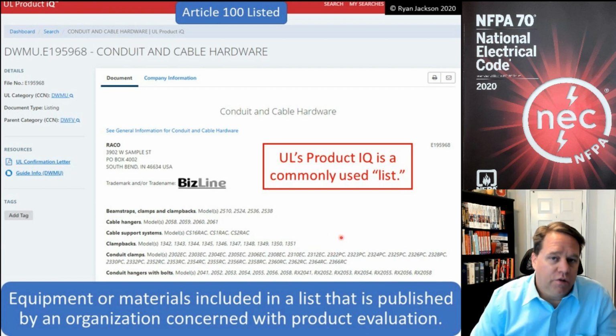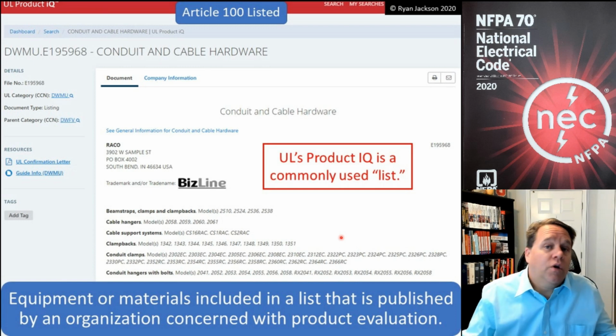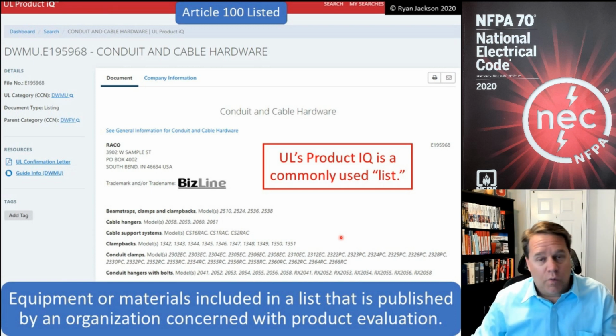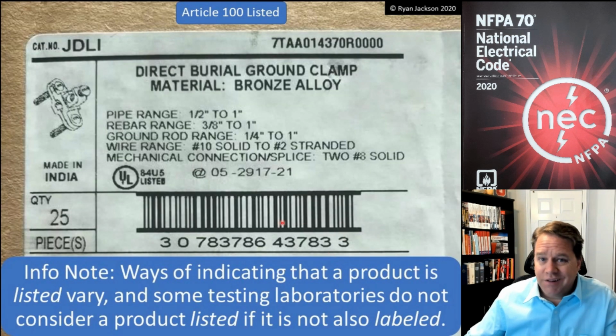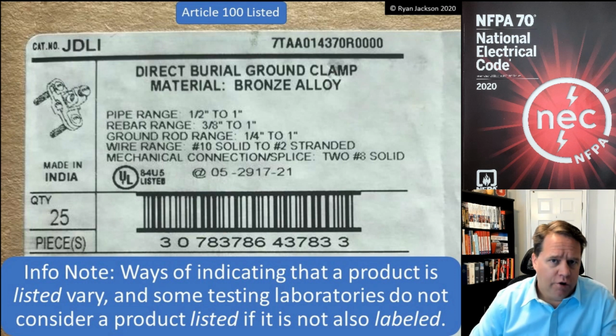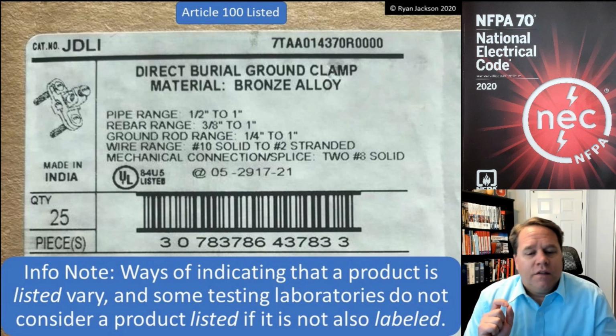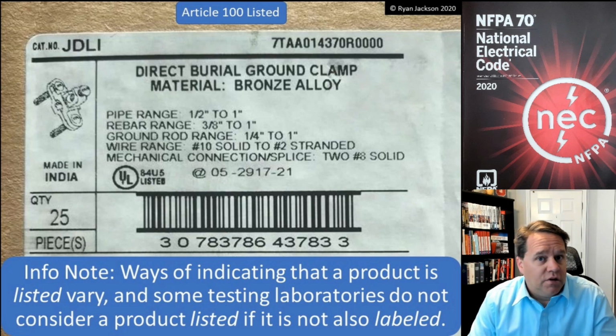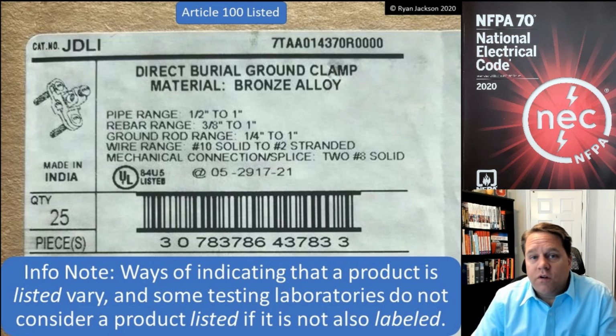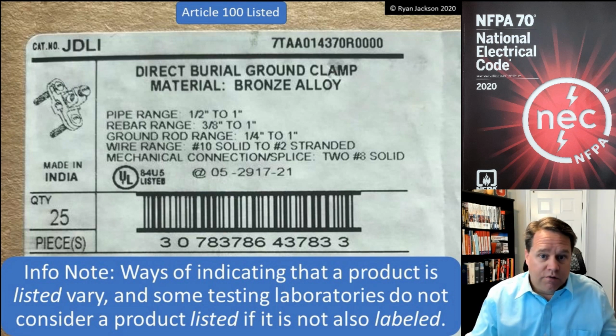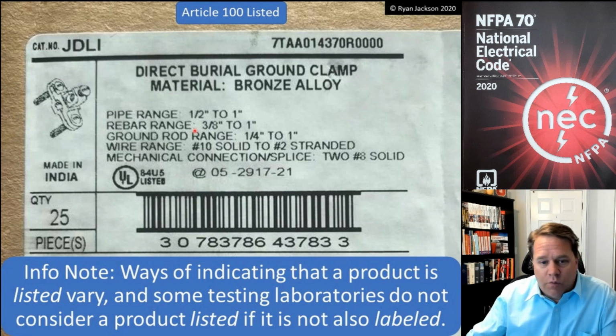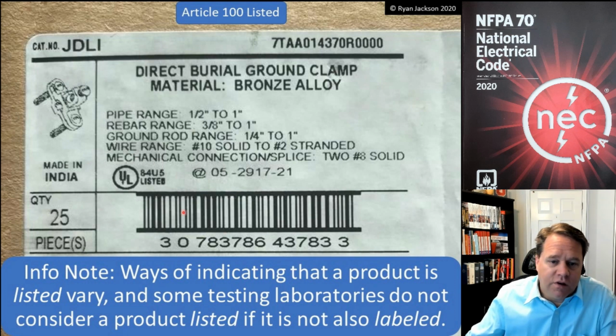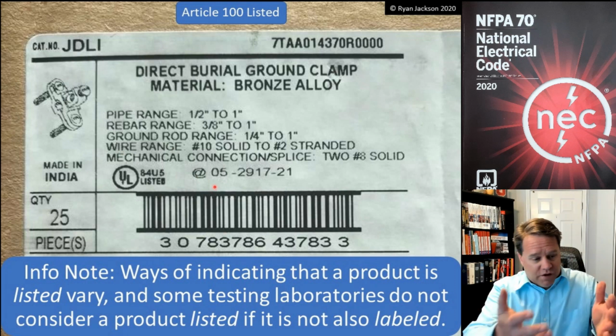Now, how would the inspector know that it's a listed product? Or for that matter, how would an electrician or anybody know that it's a listed product? Usually, the way we would do that is we're looking for a label. And there's actually an informational note here in Article 100 to the definition of listed that says, look, ways of indicating that a product is listed could vary, and some testing laboratories don't consider the product listed unless it's also labeled. Okay, so ways of indicating it vary, and it could include labeling. Well, what's labeling? Labeling is that little sticker right there. It says UL listed. Now, is that the listing? No. The listing is in the list.